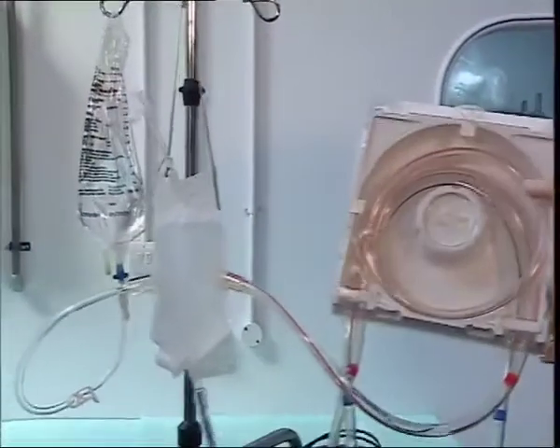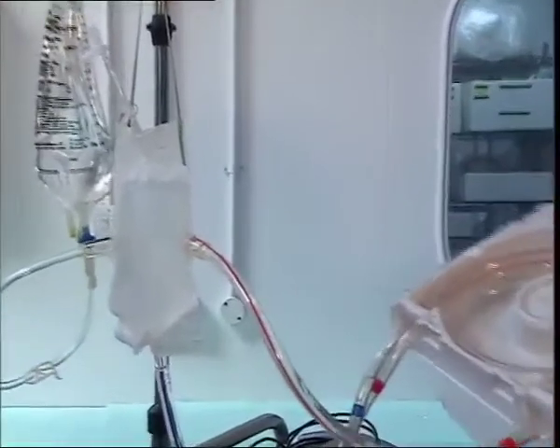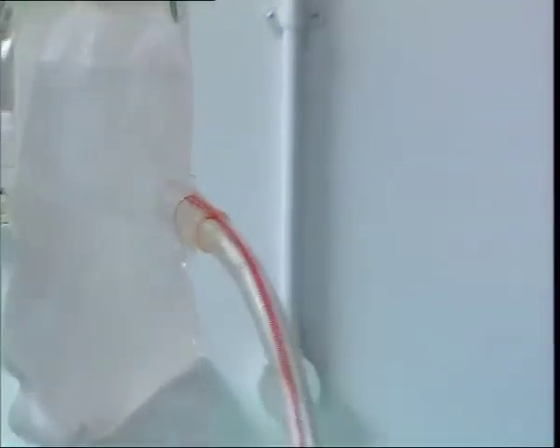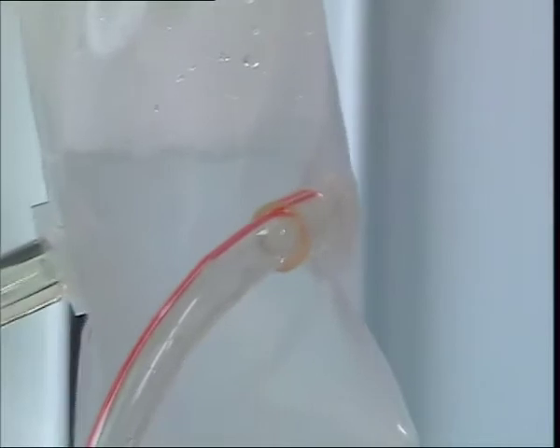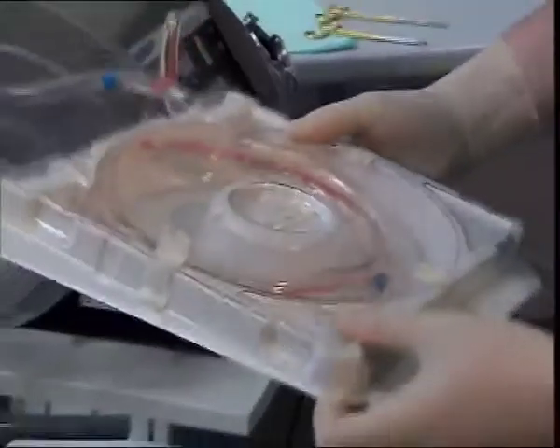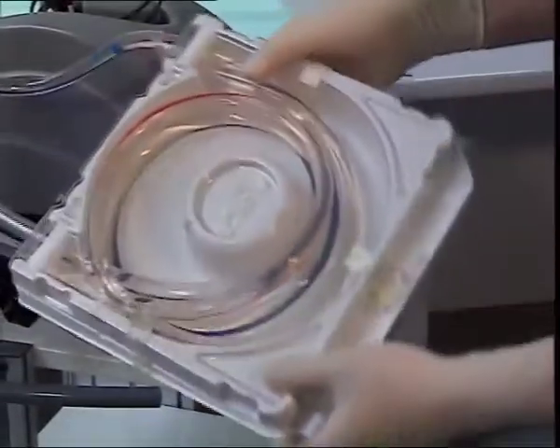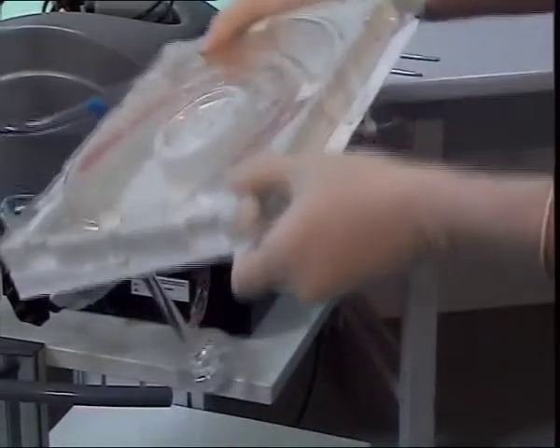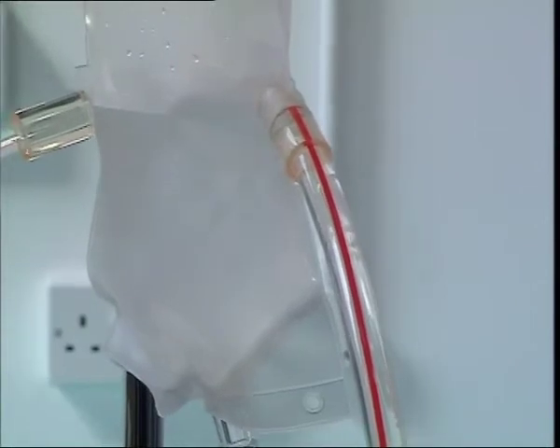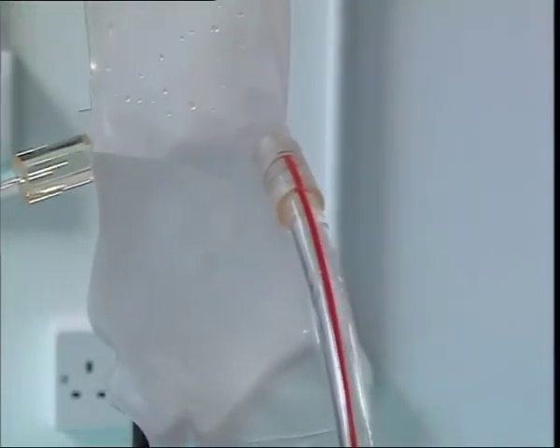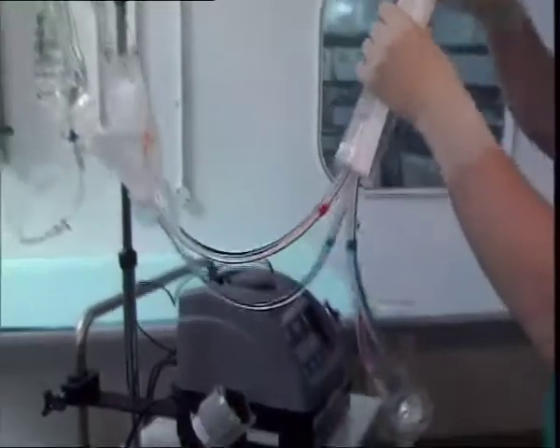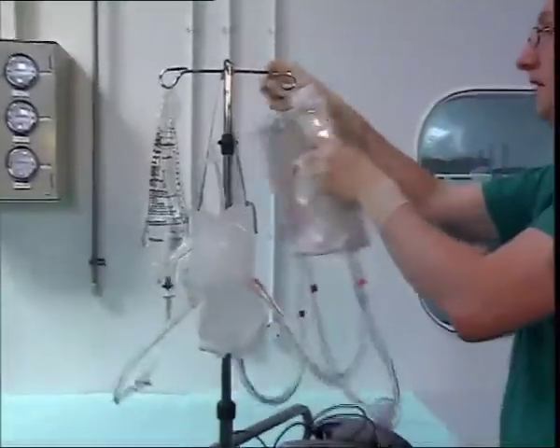Now, drop the table lines below the level of the recirculation bag. Air will rise into the bag and the table lines will fill with fluid. Try to guide any air in the system towards the recirculation bag. Once the majority of air has been removed, hang the table lines back on the drip stand.